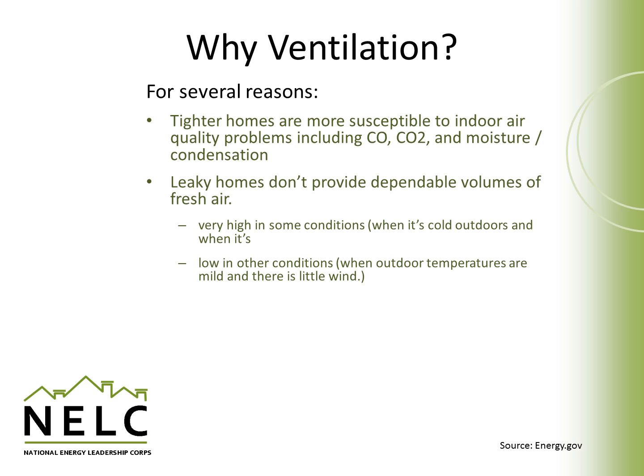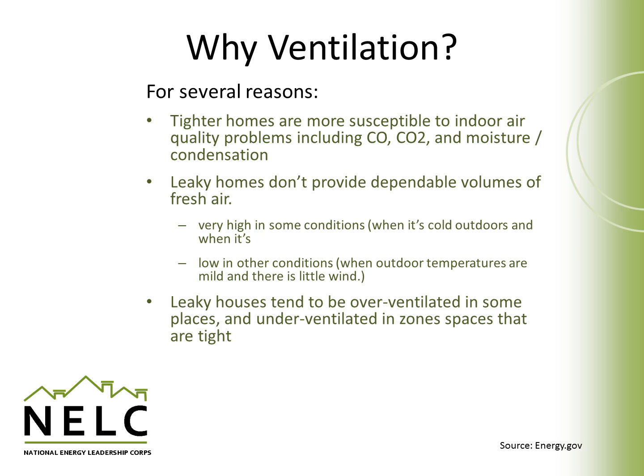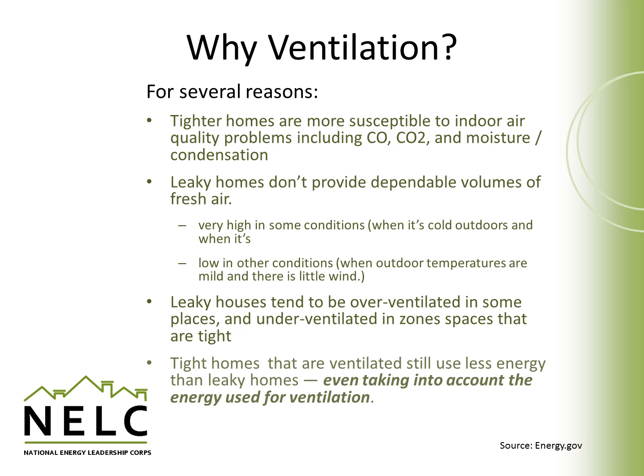Leaky homes don't provide dependable volumes of fresh air. It can be very high in some conditions, like when it's cold outdoors, and very low in other conditions, for example when it's mild or when there's very little wind. Leaky homes also tend to be overventilated in some places and underventilated in zones that are fairly airtight. Homes that are tight but ventilated will still use less energy than leaky homes, even taking into account the extra energy being used for ventilation.